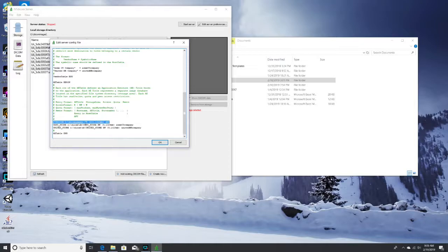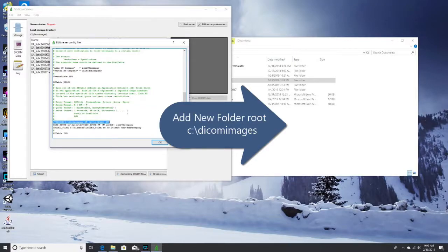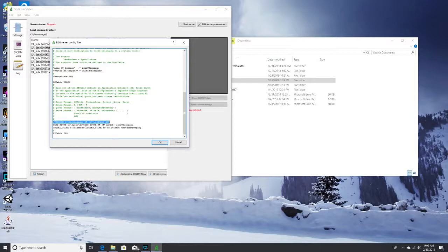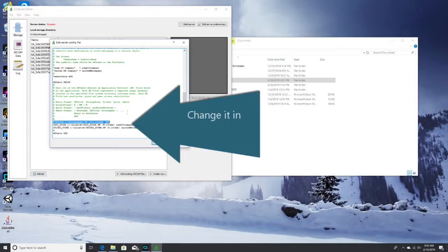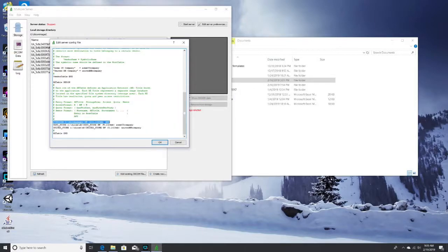Here you'll see I've already changed it. I just went directly to C, put a folder there called Dicom images, no spaces, and no weird characters. I had issues before with it. When I tried to load it, it would actually not work with the default because the only thing I can think of is it had a space in it and some characters that weren't seen, and all it would do is come up with server status starting. So I did have to go in there to edit server preferences and change that directly to a folder on C.